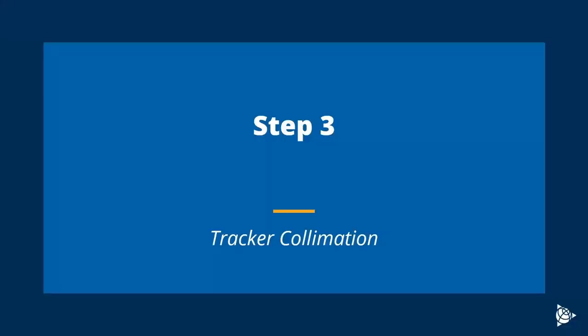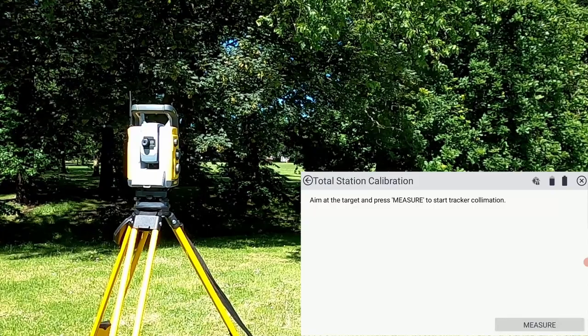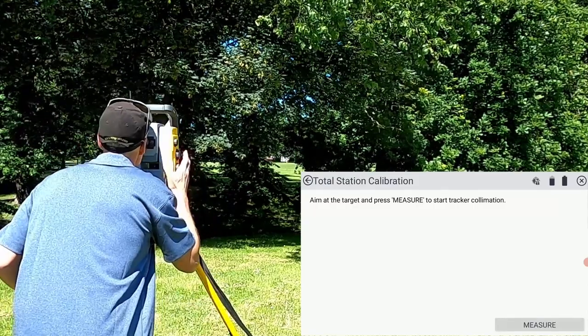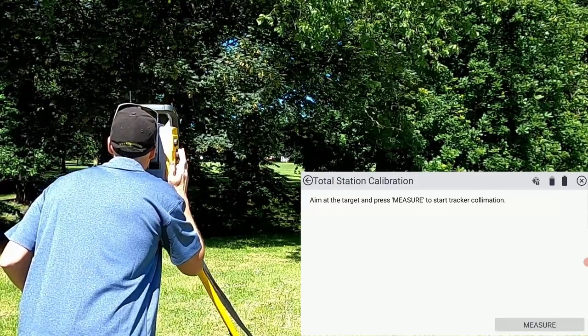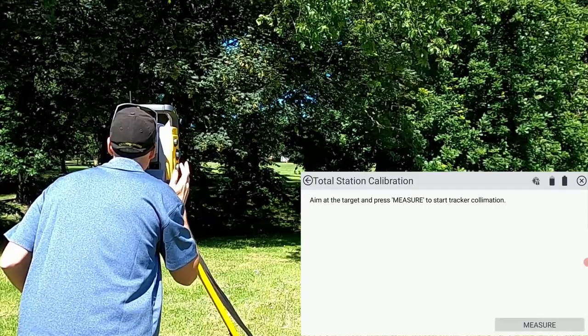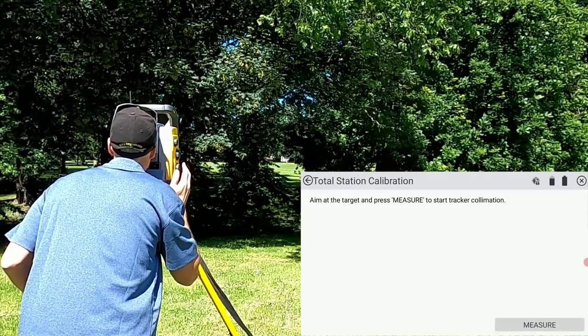The third and final step of the total station calibration is doing a tracker collimation. Make sure that you're using a multi-track target or similar in active mode because the instrument needs to actually lock onto it to take the observations on phase one and phase two.